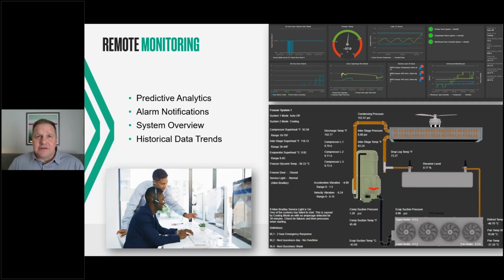One of the big items we've noticed with a lot of clients, we have over 200 connected systems, and when you come to these specs and RFPs showing that they're going to go into that box 4 times a day, as you circle back and use the data from the system, you see that they're actually in there 4 times that quantity. And that's what's causing inconsistency in the chamber temperature. So it provides both a tailoring tool so we can adjust system parameters to help correct some of that, but it also lets you explain to the customer and help them understand how their behavior is impacting their product in an adverse way.